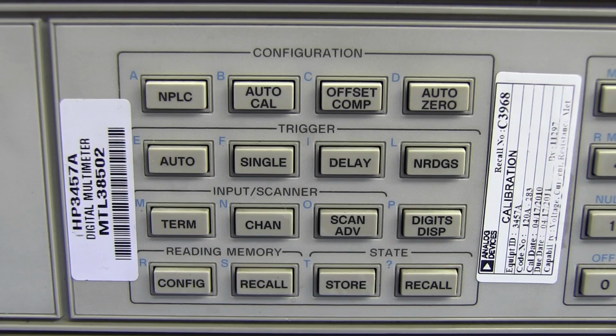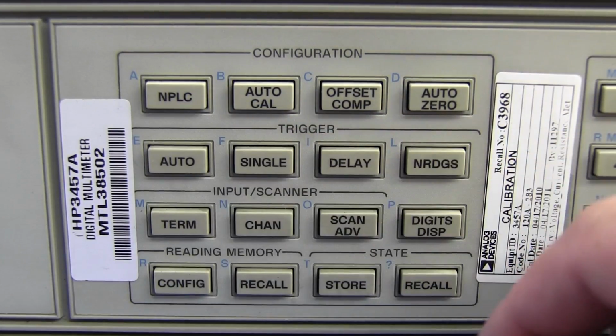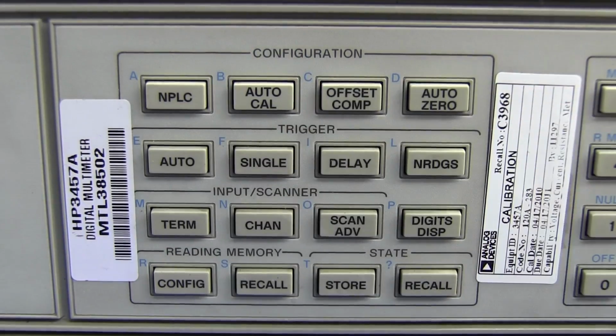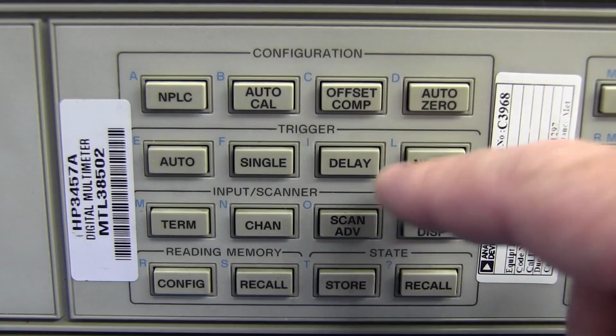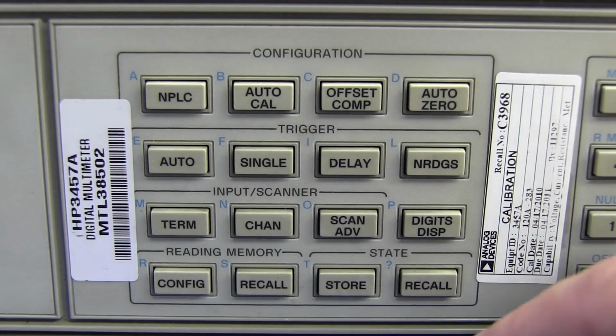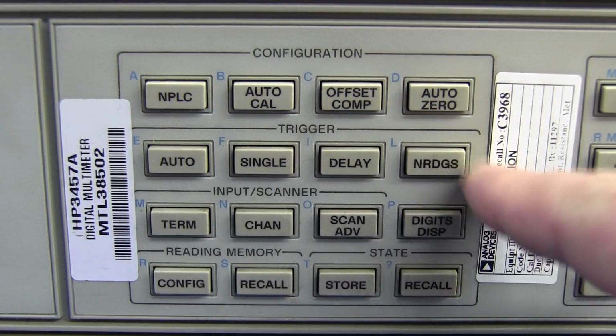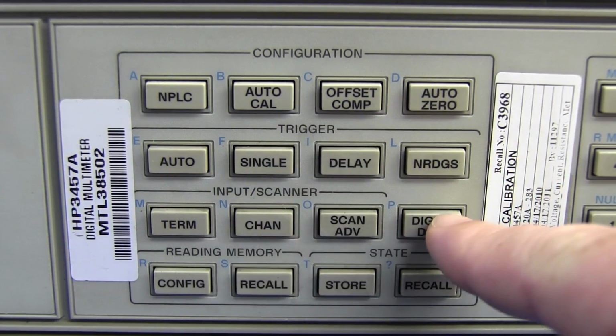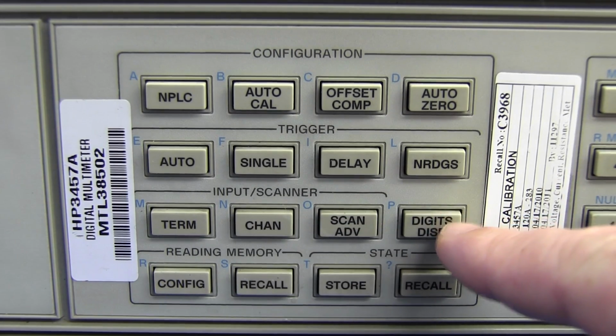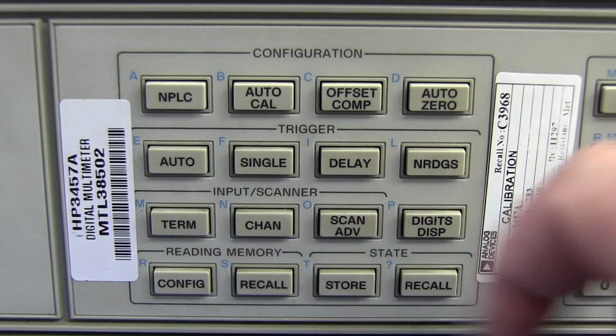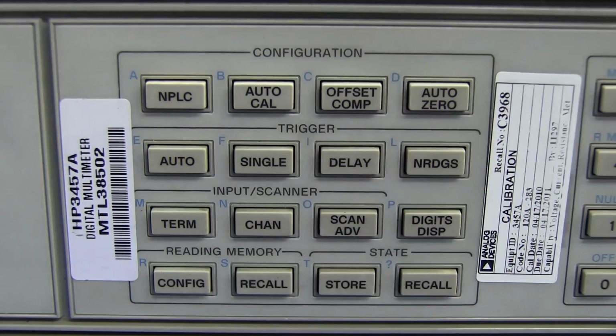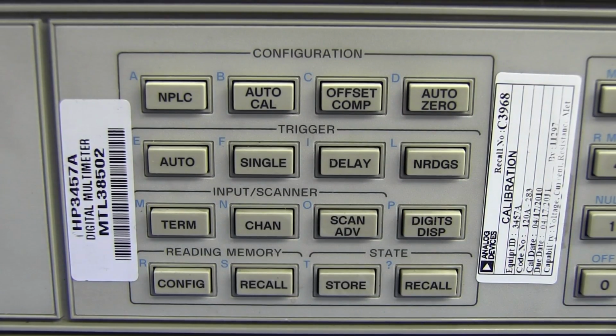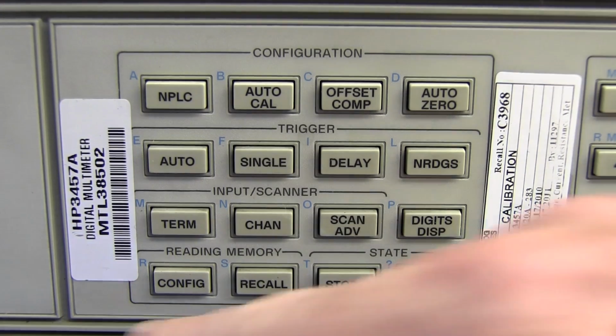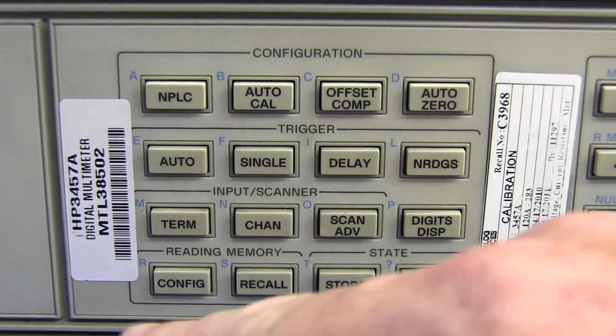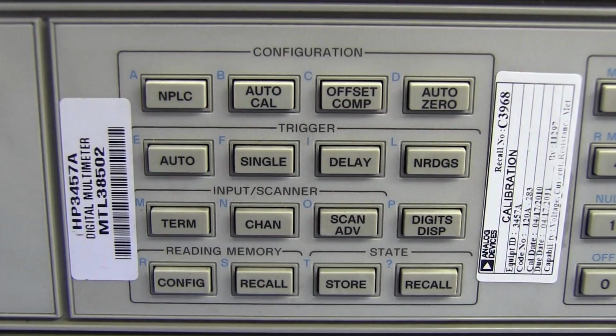And if we take a look over here at the configuration buttons, we've got number of power line cycles, so you change the integration time, effectively the update time, and that averages things out for you. It's got auto calibration, auto zero, offset compensation, various triggering capabilities, and an optional input scanner as well, but they're usually a very expensive option, so you can have multiple input channels. As we'll see, there's a slot on the back to actually do that. This one's not configured with that, and you can store and recall various configuration settings.